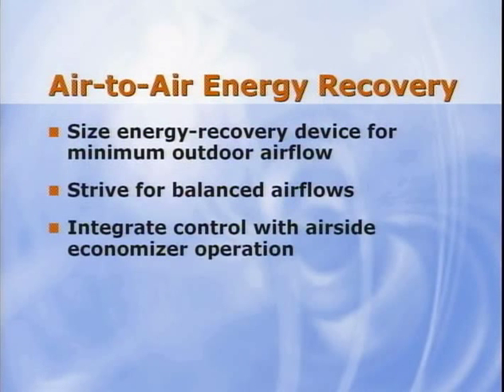On a related note, in a system with a smaller percentage of outdoor air, restroom exhaust and leakage due to building pressurization may result in very little centralized exhaust during non-economizer modes. In this case, energy recovery might not provide much benefit. Third, integrate control with Airside Economizer operation. In many climates, an economizer can provide the benefits of free cooling for much of the year.